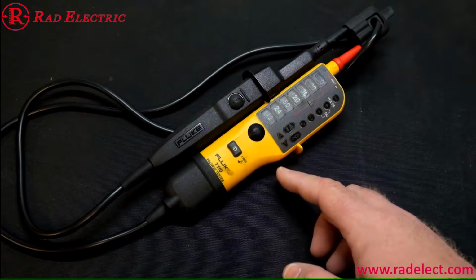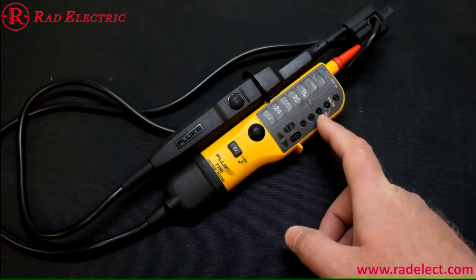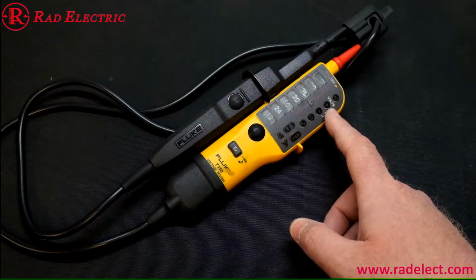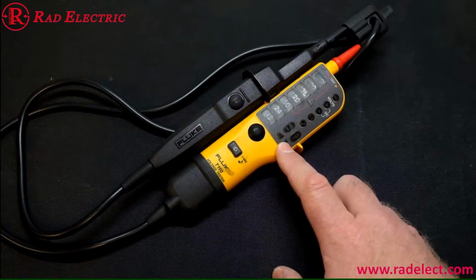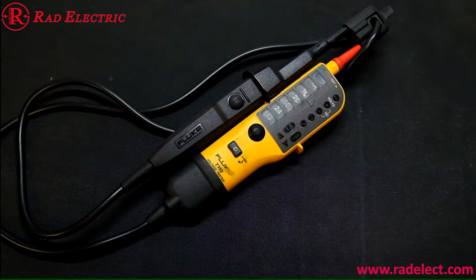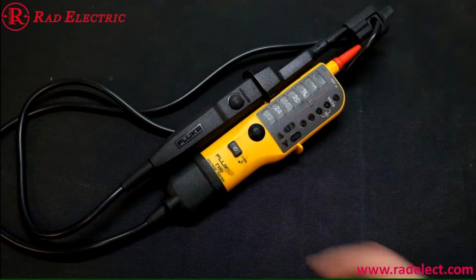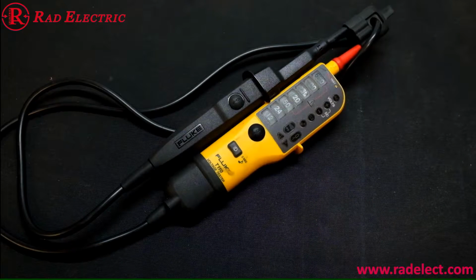This one here can do AC and DC. It can tell you whether it's AC or DC, the polarity of the DC if it is DC, the phase rotation. It can also check continuity, and it can simulate an earth leakage at a very basic level. It also has a built-in torch, which is quite nice.